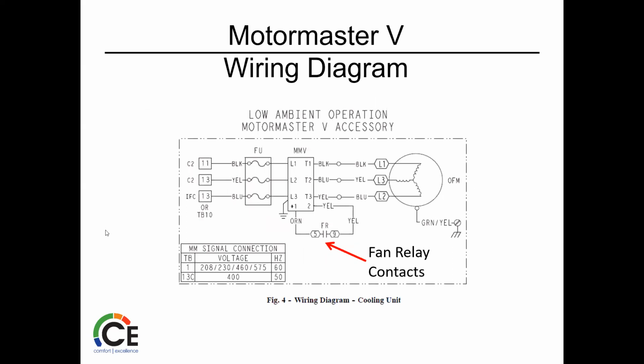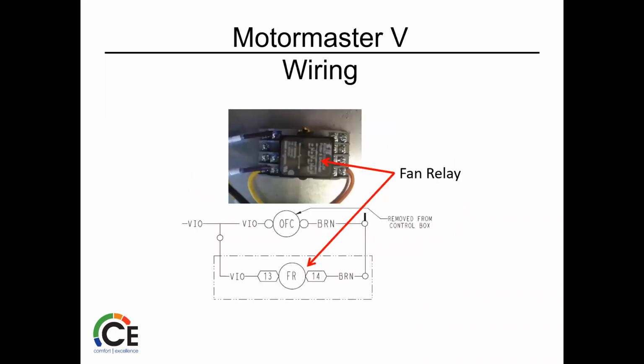So again, there's your fan relay contacts. You can see you just wired it in there. Orange off of number 1, number 2, which goes to your fan relay. Everything else here is your line voltage in. There's your motor master control. So we're putting the power into the motor master and then letting it out to our fan motor, just like the indoor VFDs, right? Everybody's favorite. So again, there's the outdoor fan contactor. We got your fan relay wiring.